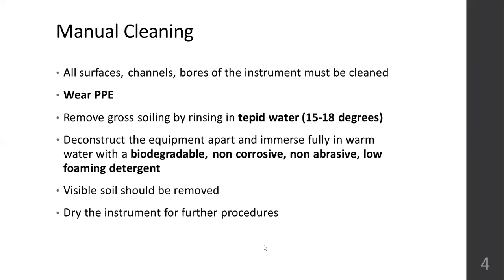When you're doing manual cleaning, if any equipment requires deconstruction, disassembling the instrument or equipment has to be done, and each and every part has to be fully immersed in warm water with a detergent. Ideally, the detergent should be biodegradable, non-corrosive, non-abrasive, and low foaming. All the visible soil should be removed, and after this you have to dry the instrument for further procedures, either sterilization or disinfection.